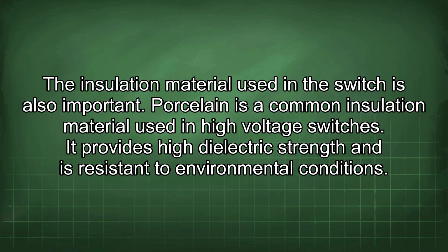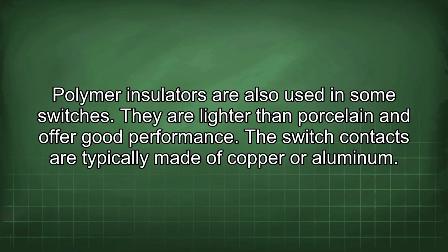The insulation material used in the switch is also important. Porcelain is a common insulation material used in high-voltage switches. It provides high dielectric strength and is resistant to environmental conditions. Polymer insulators are also used in some switches. They are lighter than porcelain and offer good performance.